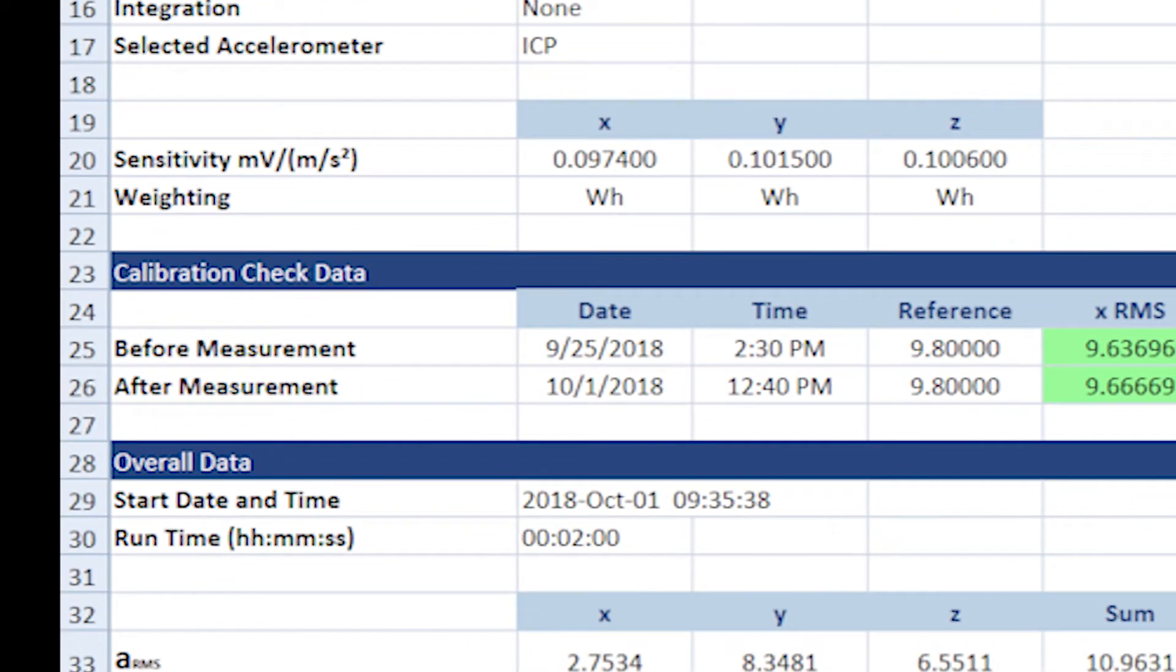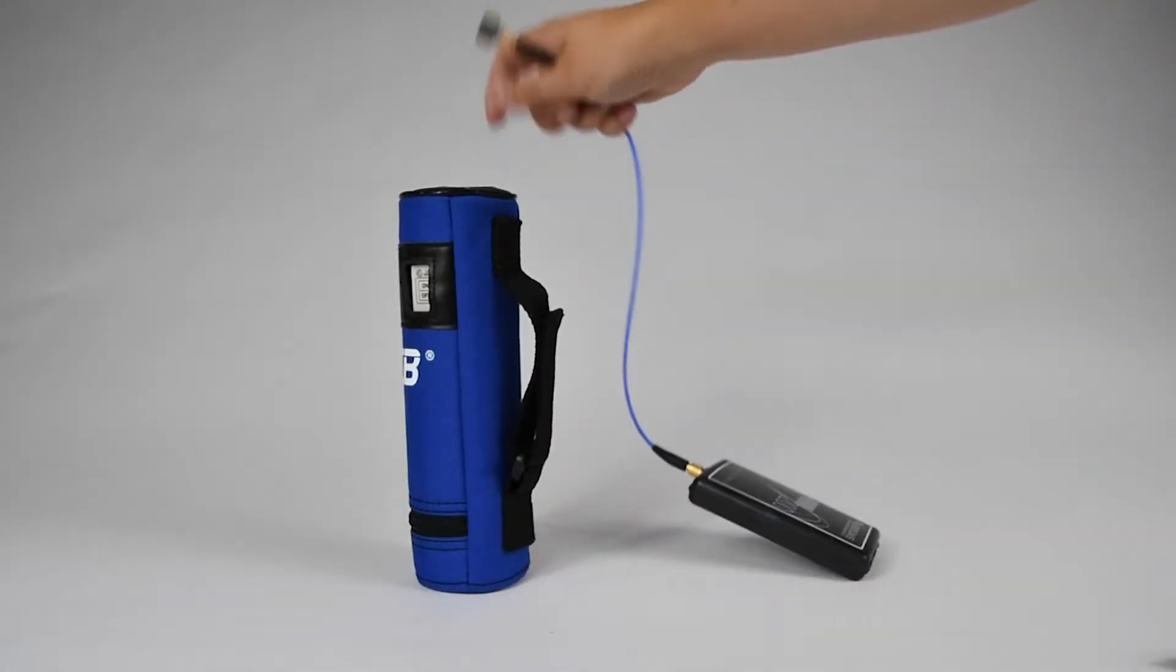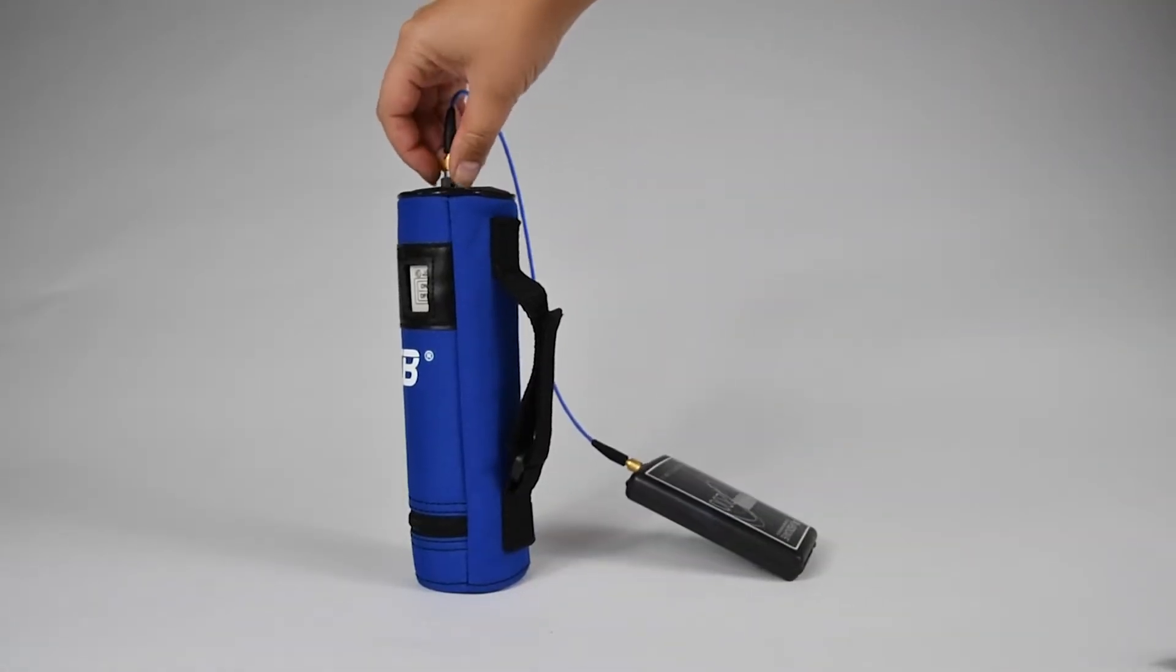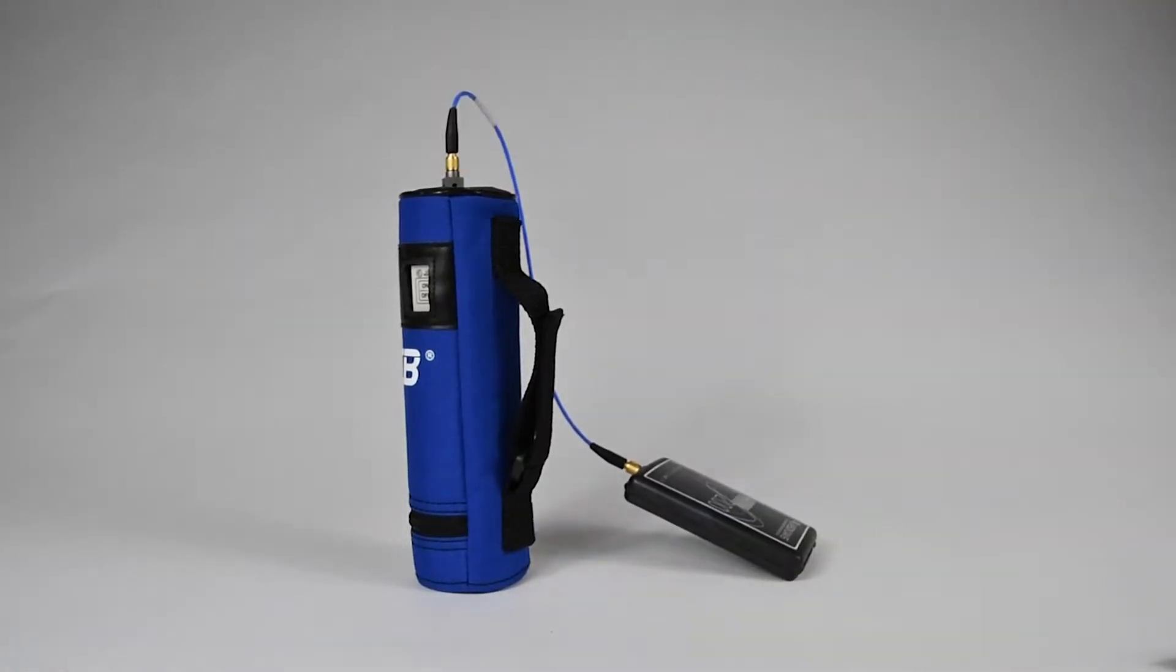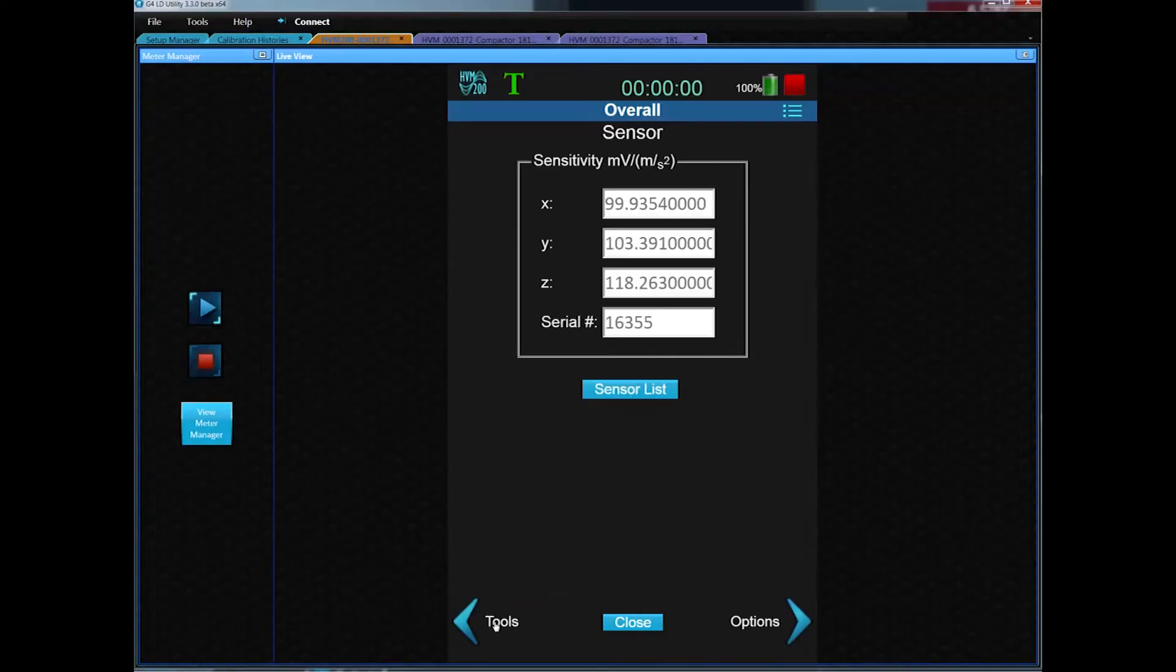This example is using the SCN040F sensor, which will need the sensitivity data entered in manually. Some sensors may be equipped with TEDS, which the meter will read the TEDS sensitivity and enter it in automatically.